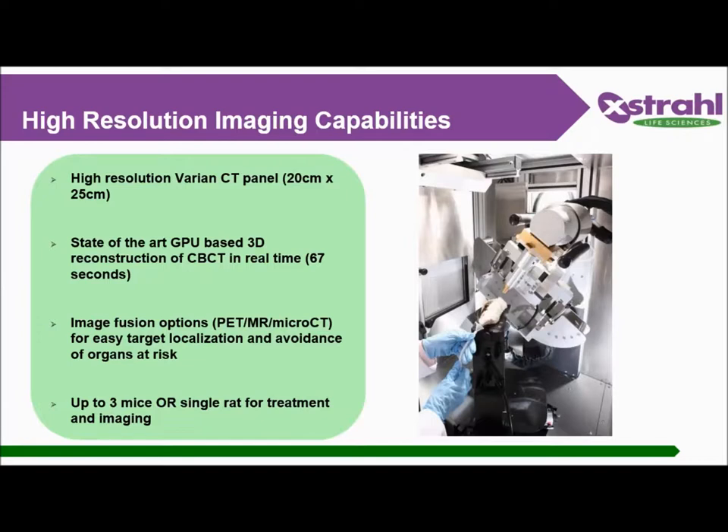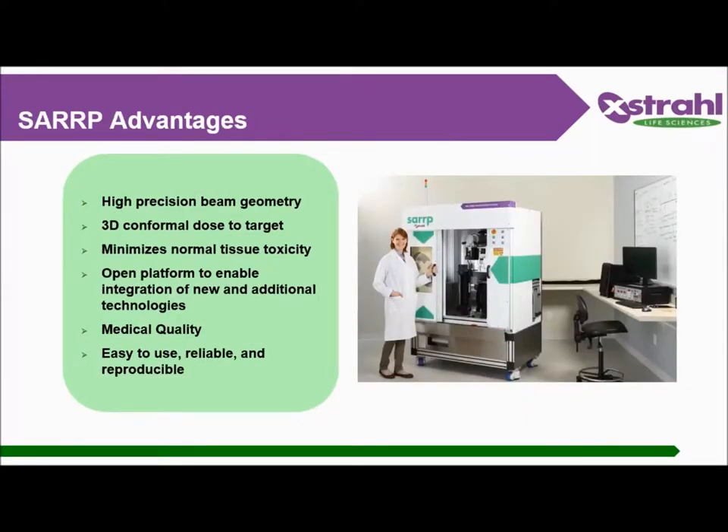Acquiring a CT takes only 67 seconds, with reconstruction happening at the same time, so as soon as your CT ends it is already loaded in your TPS. The system is medical quality — Xstrahl is both a life science and a medical device company, so they use the same components for both types of equipment, which assures reliability. The system is very accurate and allows for reproducible results. It's an open platform, meaning when new technology is developed it can always be easily adapted to the system you already have.